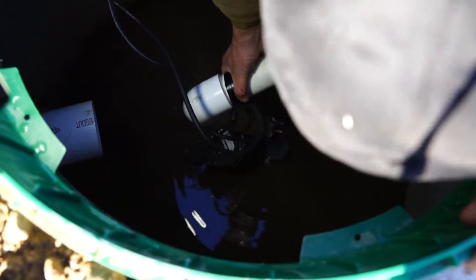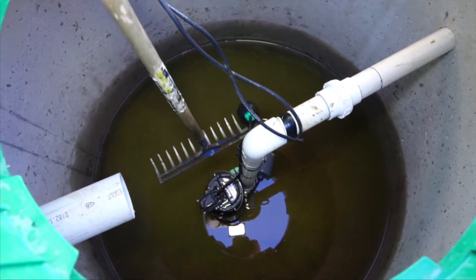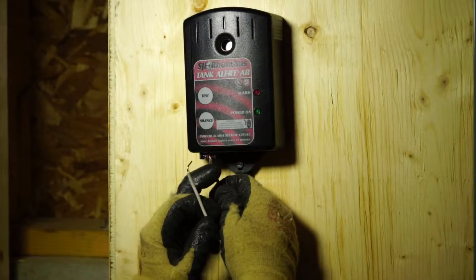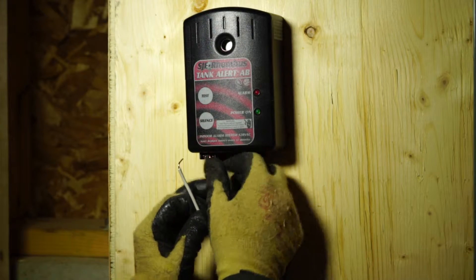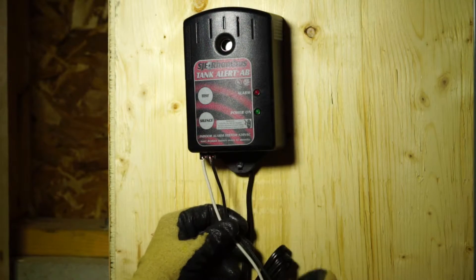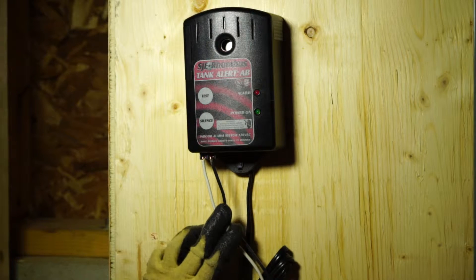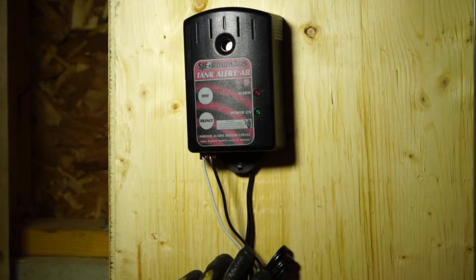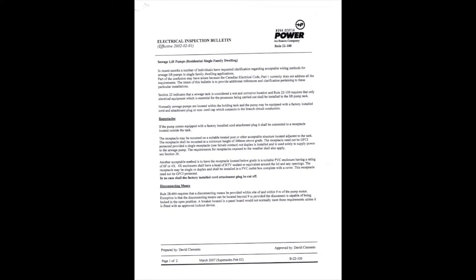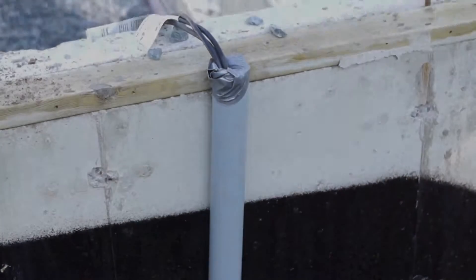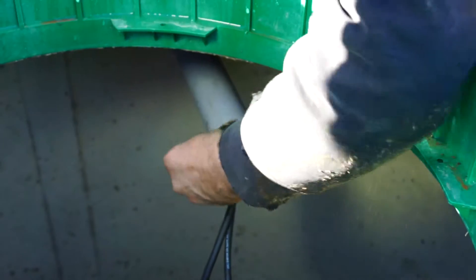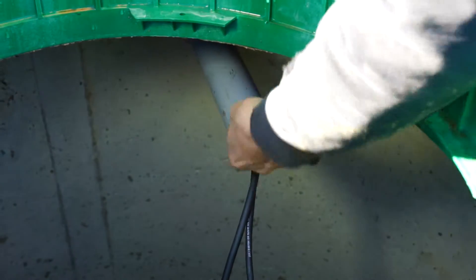The pump is installed in the pump chamber, and on-off and alarm floats are set to proper levels. Visual and audible alarms are installed in the home and connected to the alarm float. The pump is connected to a receptacle according to the electrical code.